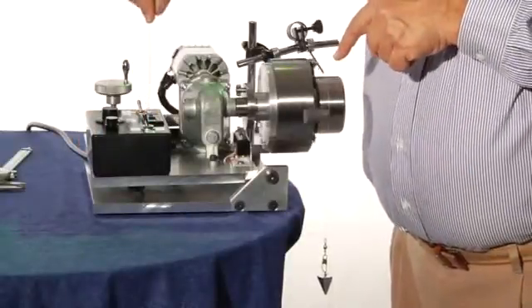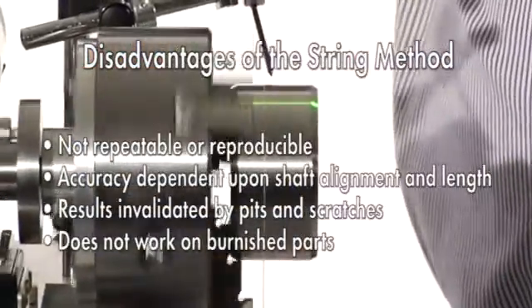Although this string method has been the industry standard for over a decade, it has widely known disadvantages and failings. It has proven to be qualitative rather than quantitative because the results can vary from operator to operator and depend heavily on the level and wobble of the shaft at setup, as well as the surface finish of the shaft during measurement.